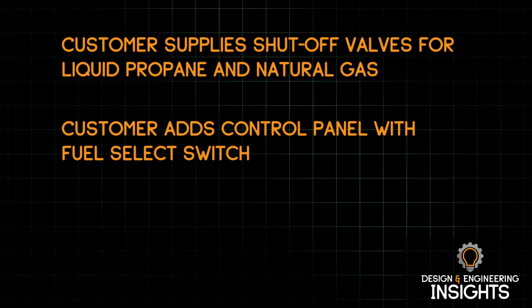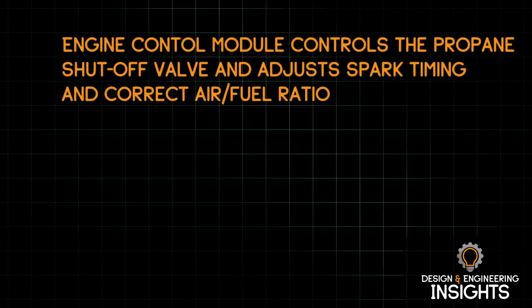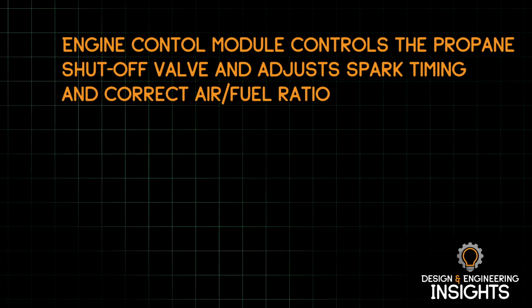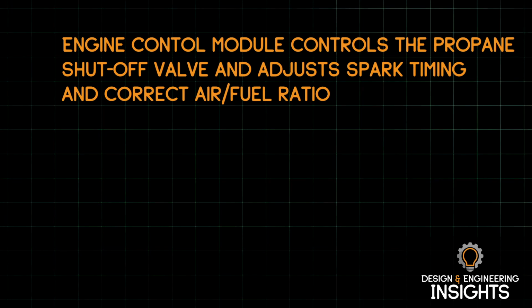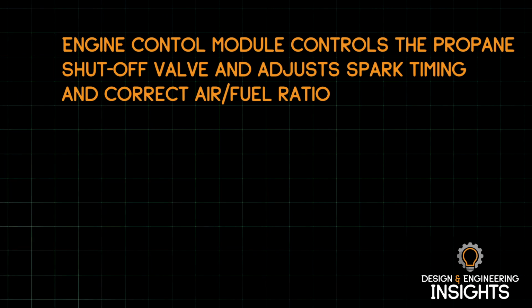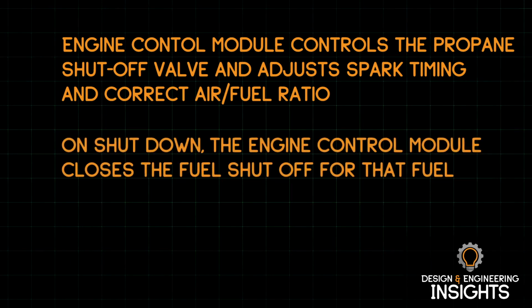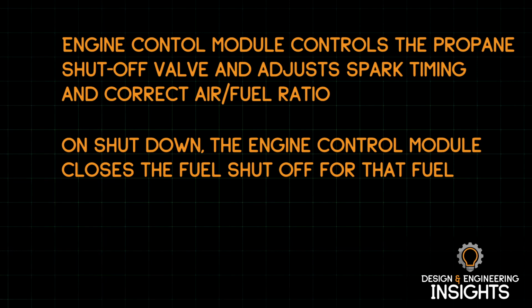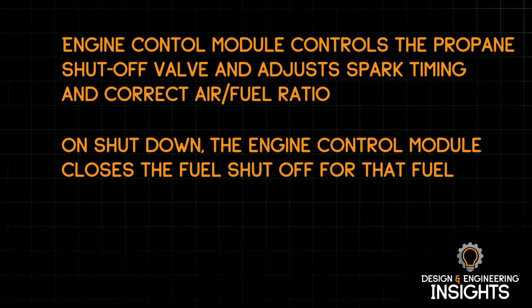Once the fuel select switch is set to a given fuel, let's say propane, for example, the engine control module will control the propane shutoff valve. So on a key start, the shutoff valve would open and allow liquid propane to flow. The control module would also tell the engine to run on the spark timing and air fuel ratio for that given fuel. Then on a shutdown, the engine control module would close the fuel shutoff for that fuel and shut the engine down. So that's a basic overview of how the system operates.